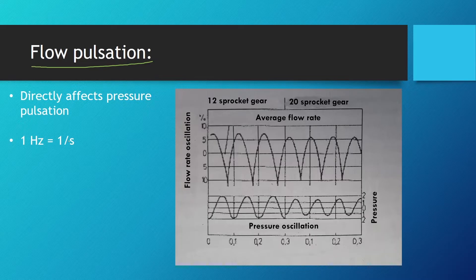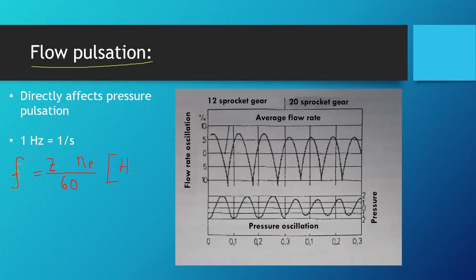How do we calculate flow pulsation? First, let's calculate the frequency of the pulsations. The frequency f equals z, the number of teeth, times the speed in rotations per minute, divided by 60. This gives frequency in hertz. One hertz means it happens once per second; 60 hertz means 60 times per second. One hertz is essentially one divided by second, or second to the minus one. The pulsation of flow impacts pressure and makes noise while the pump works.